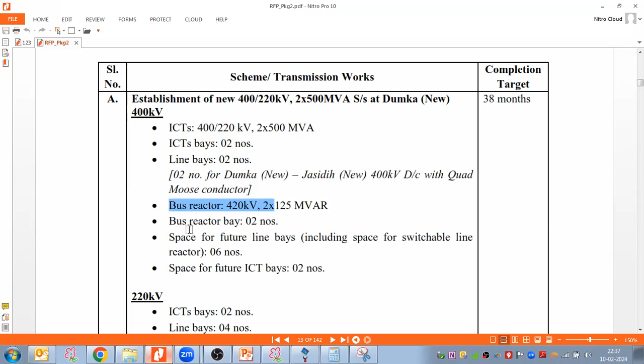And on which line it will connect, we have to check with the owner, with the client, to see on which line you require the reactor connections, the shunt reactor connections. Coming back to the reactor connections, as I told, there are two types of shunt reactor connection possible in substations: line shunt reactor, meaning reactor connected in shunt of a transmission line, or bus bar shunt reactor, meaning reactor connected in shunt of the common bus bar. Transmission line shunt reactor can be...